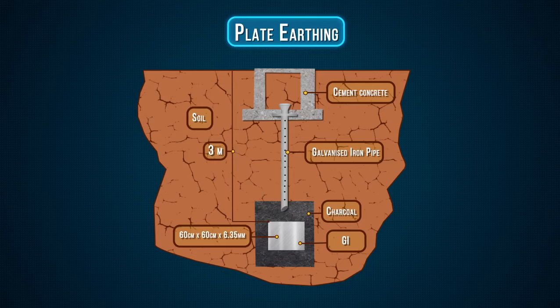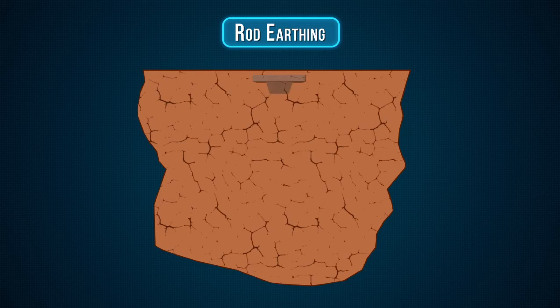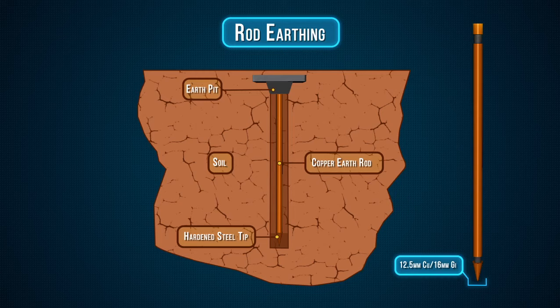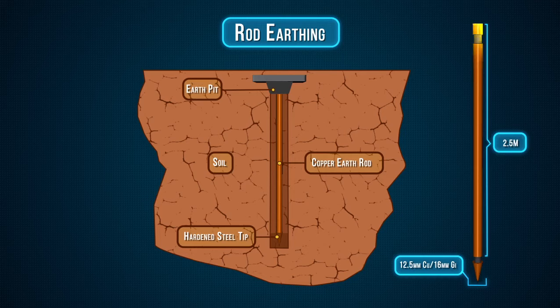Rod earthing. Look at this design for details. A copper rod of 12.5 mm or 16 mm diameter, or galvanized steel of length above 2.5 m, are buried upright in the earth manually or using a pneumatic hammer. The length of embedded electrodes in the soil reduces earth resistance to a desired value.